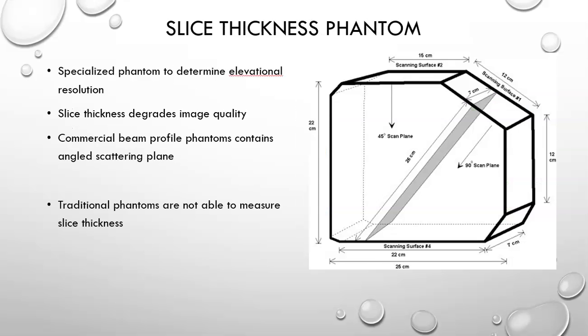A slice thickness phantom is used to evaluate elevational resolution. It's just like the rubber band on the angle iron that we utilized in our lab. The only difference is that it's more consistent than what we used in the lab. The commercial ones are very expensive, so I haven't picked up one of those yet.